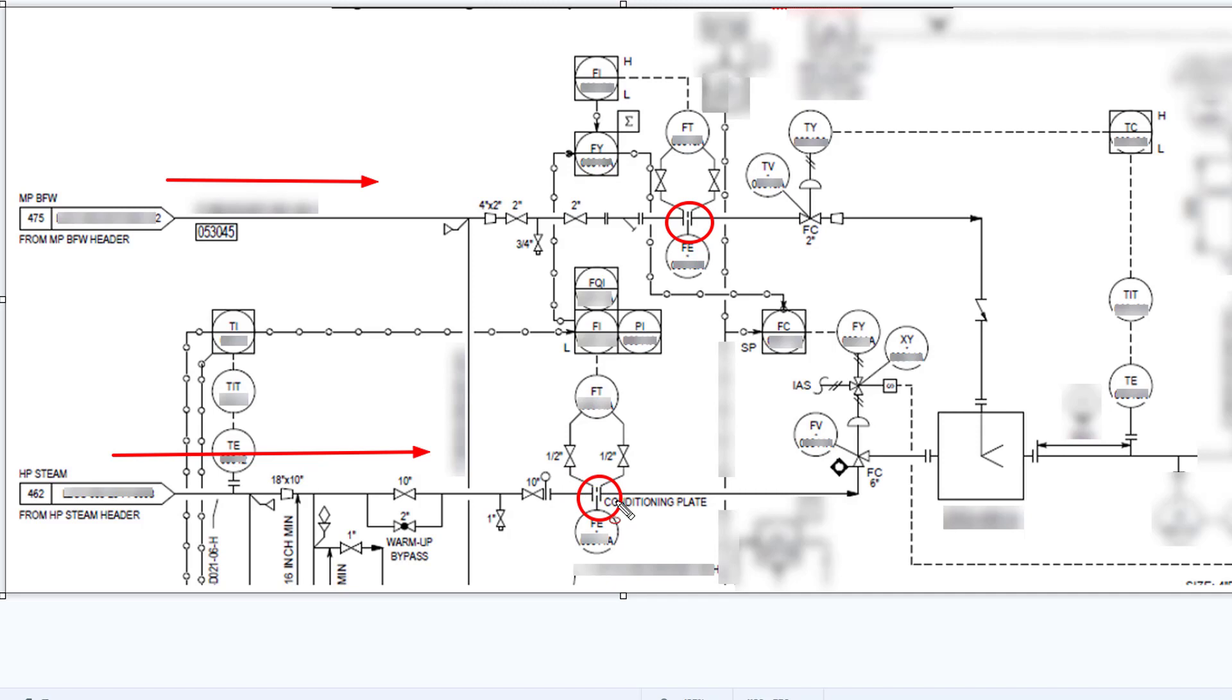Given the problems with turndown on these types of installations, it's quite common not to use flow control, but sometimes you can. It does linearize it if you are in a reliable region always. The first thing is you need a specialized device, which is shown here, and this is normally a special item from the vendor which is a desuperheater where you're injecting the water into the steam.